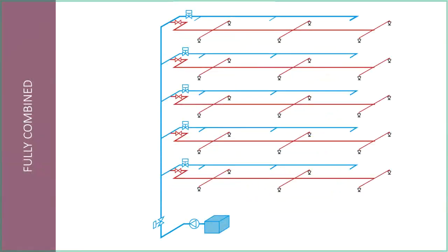This one is a fully combined system. What I should have done is put some labels on here, because we have priority demand valves on each floor level. You don't necessarily need one on each floor level. You could just have one at the bottom. It just depends on whether you have a shared riser or not. If you've got a combined riser, as you can see, that's for the domestic supply and the sprinklers, then you're going to need a priority demand valve on each floor.